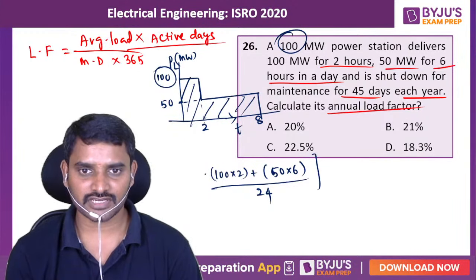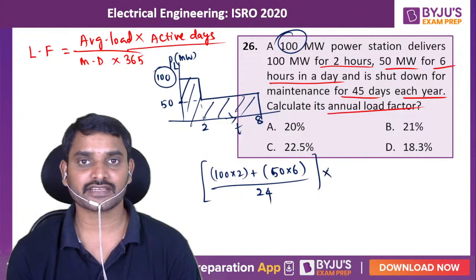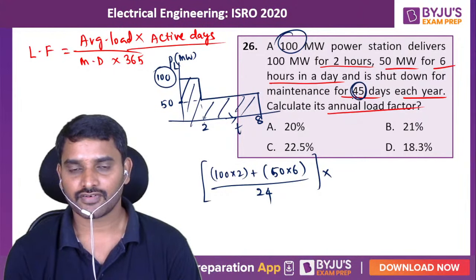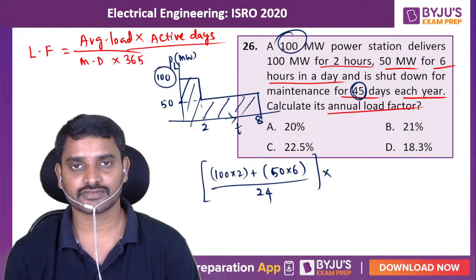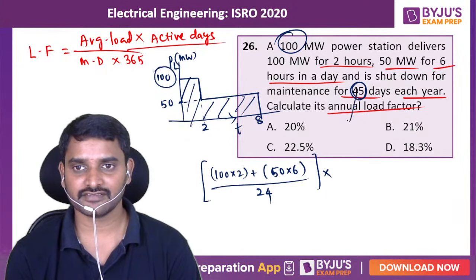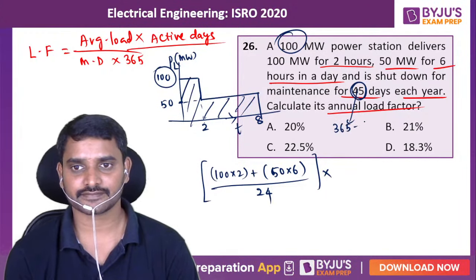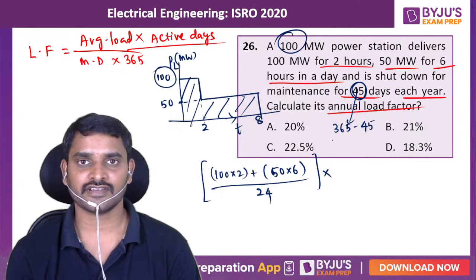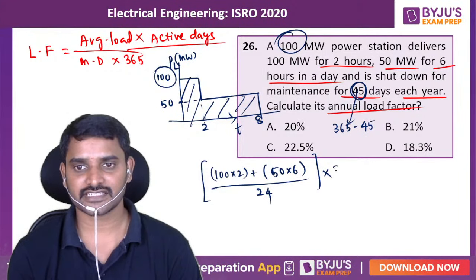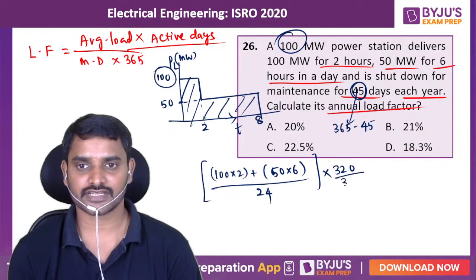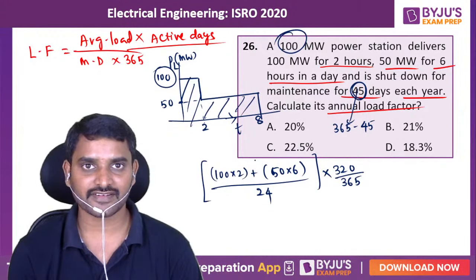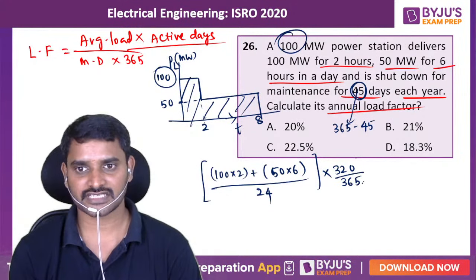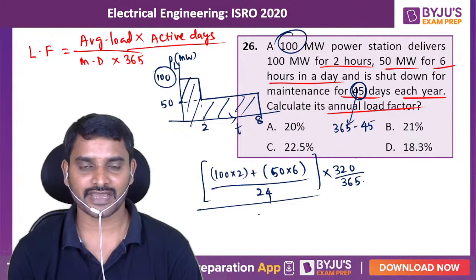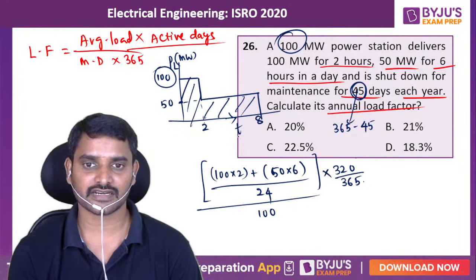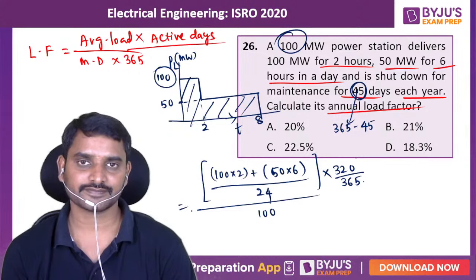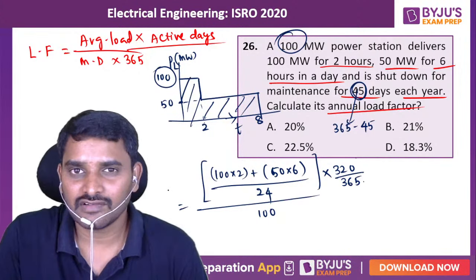How many days it is going to be active? 45 days it is going to be shut down. So that means 365 minus 45 days. So it will be around 320 days it is active out of 365 days. This is the average load, active days over 365 days and divided by maximum demand. If you take up maximum demand as 100, so this could be the answer. Solve it, you will get the answer.